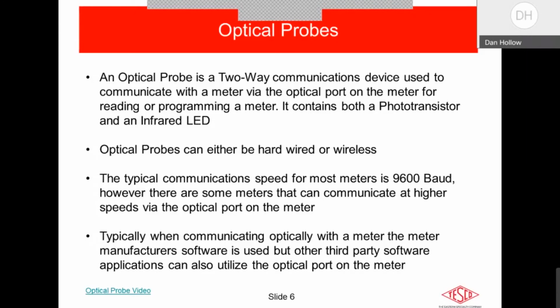And there are basically two flavors of optical probes in modern day metering. The original one obviously was a hardwired optical probe, and there were various manufacturers throughout the years that made optical probes, some of which are still in business, others have gone by the wayside. A lot of the meter manufacturers also made their own optical probes. Ideally, the term came out in the early 90s, I believe, is when I first heard it, of a universal optical probe. Universal optical probe simply means that the optical probe was universally compatible with all types of meter manufacturers. So it would work on a GE Aclara meter, it would work on an Itron meter, it would work on a Landis and Gyr meter, it would work on an ION meter, it would work on whatever meter, Honeywell, Elster. So those were universal optical probes.